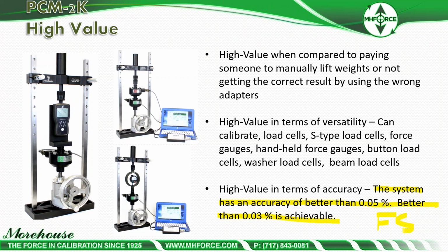So if we're at 0.003 at full scale, typically you could say, hey, at 10% we'd be at 0.03. That ratio doesn't always hold because there's different resolution. Some things become dominant. Remember, when you're doing uncertainty, you're putting everything together to make up that uncertainty. So speccing it at full scale is pretty rough because it's not always the same, and it does not scale down in a linear fashion. So watch that. This implies if you want better than 0.03%, said it's achievable, that means you're changing a standard at about every 20% of the range.